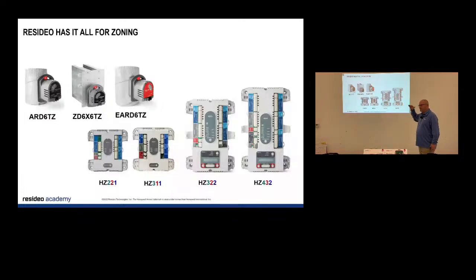Make sure the smallest zone is at least 60% of the total CFM. So what's 60% of 2,000? 1,200. I need to make sure I've got enough ductwork. If the other zones close, I can jam 1,200 CFM down that duct. If I don't, you need to use a bypass damper, and I'll get into bypass dampers. But you can get away from bypass dampers if at least 60% of your load CFM-wise can dump into 1 small zone. That'll keep you out of a lot of trouble.